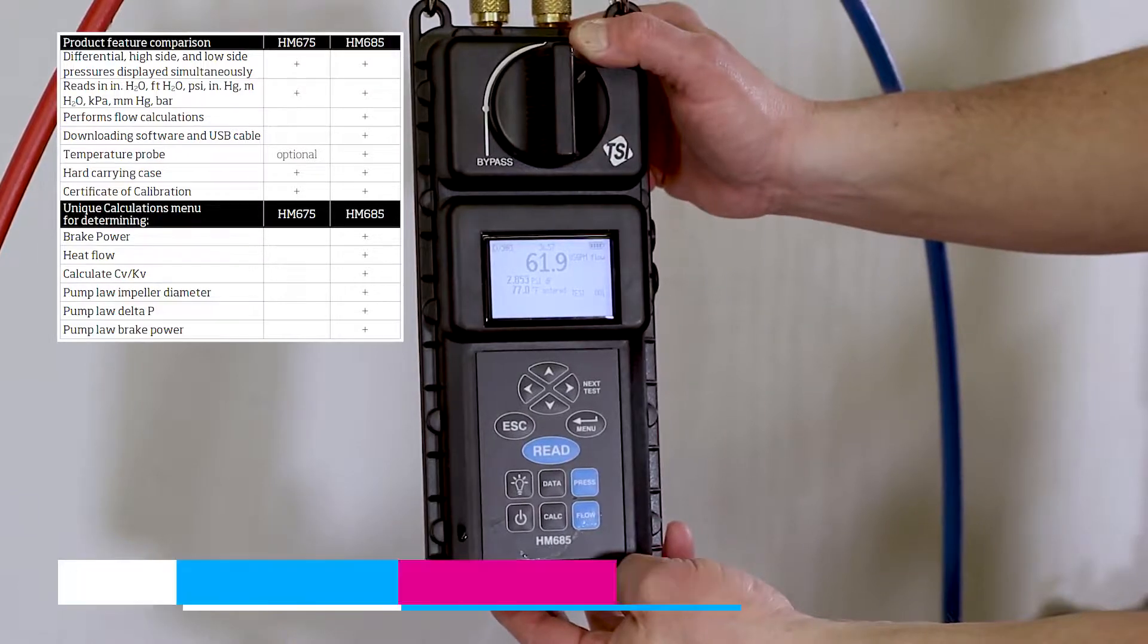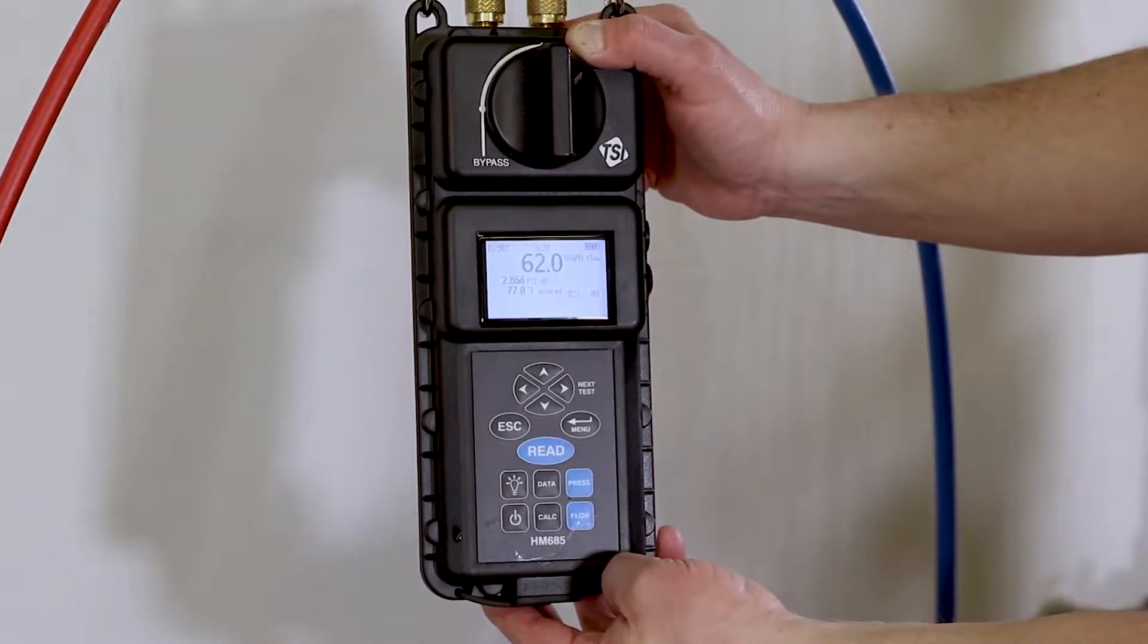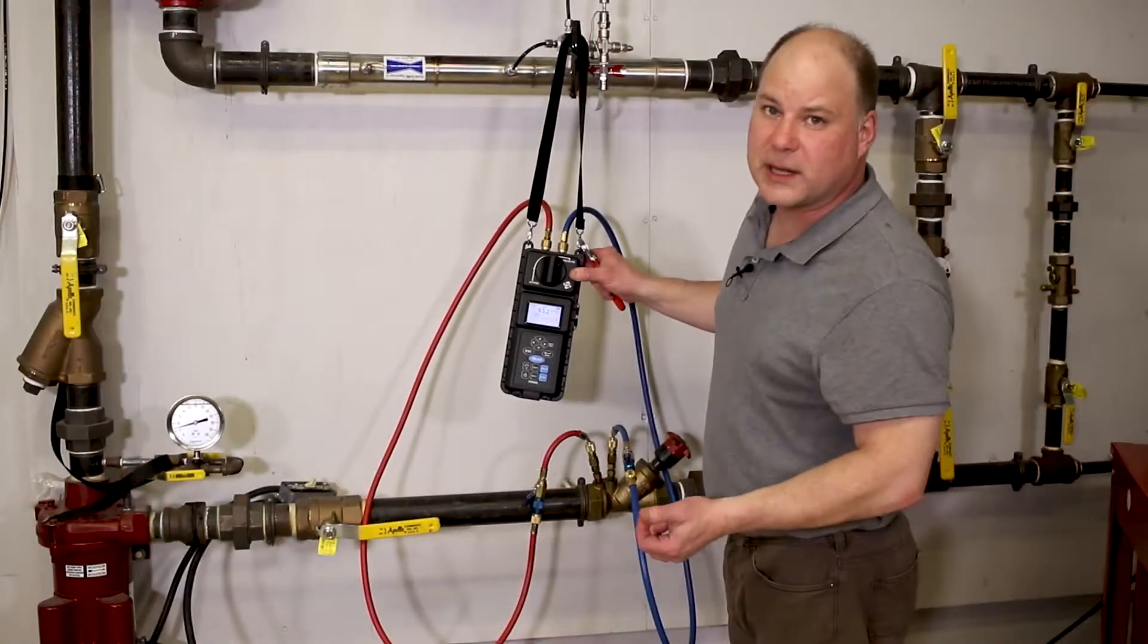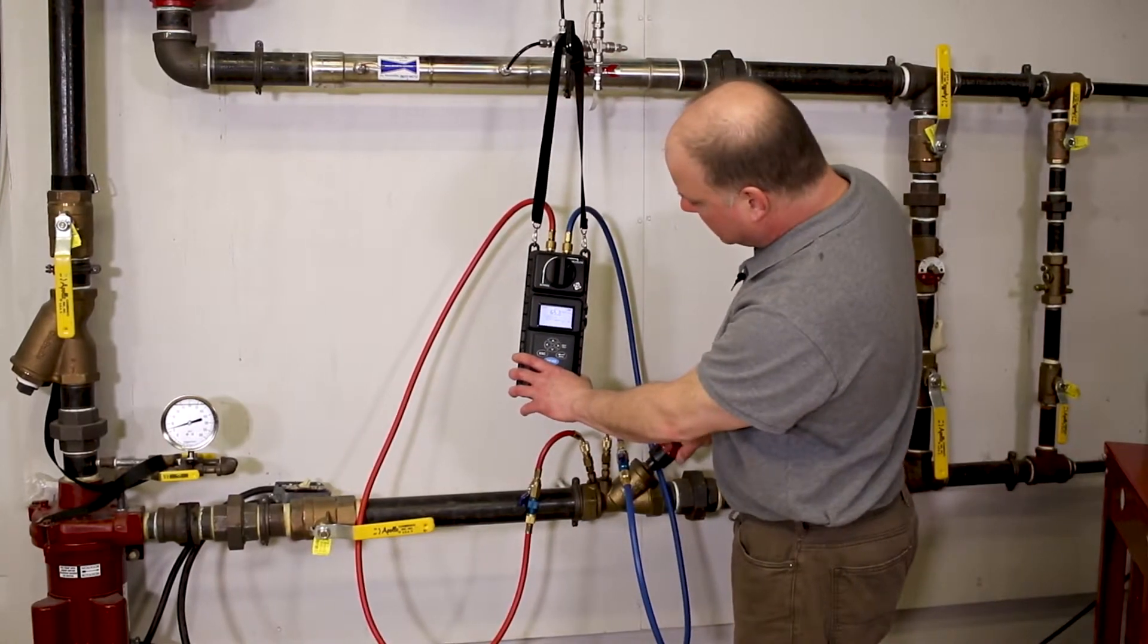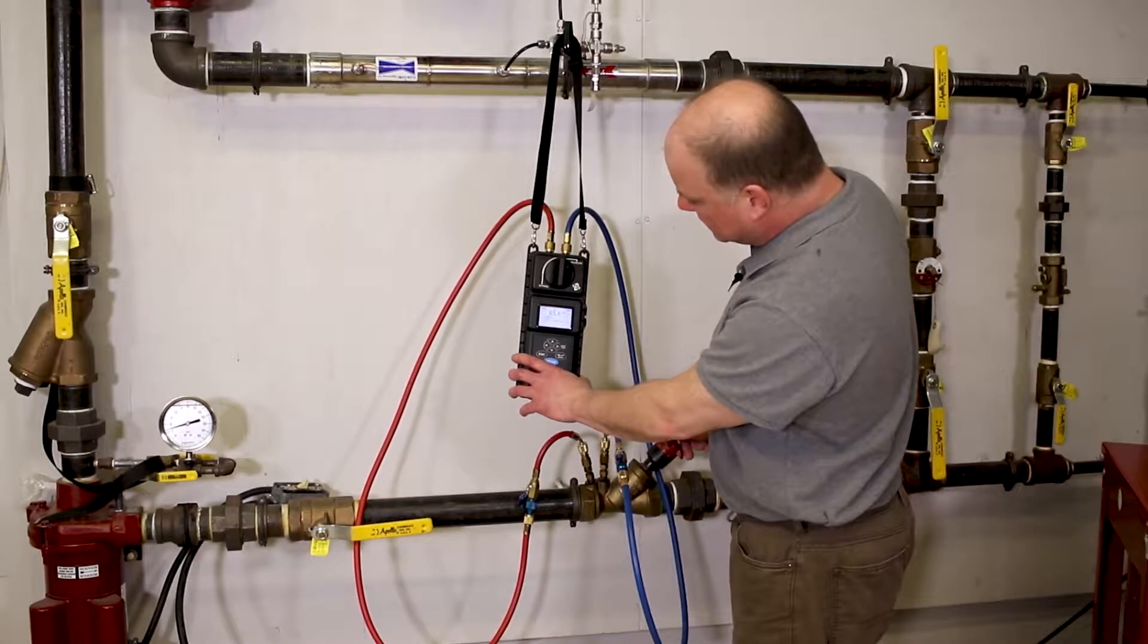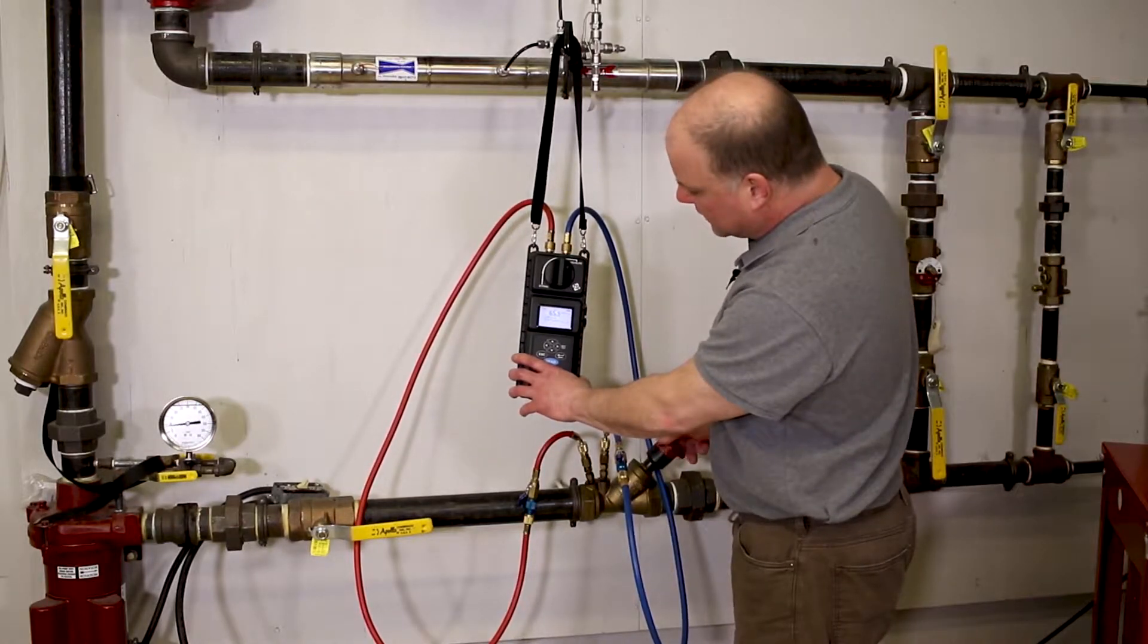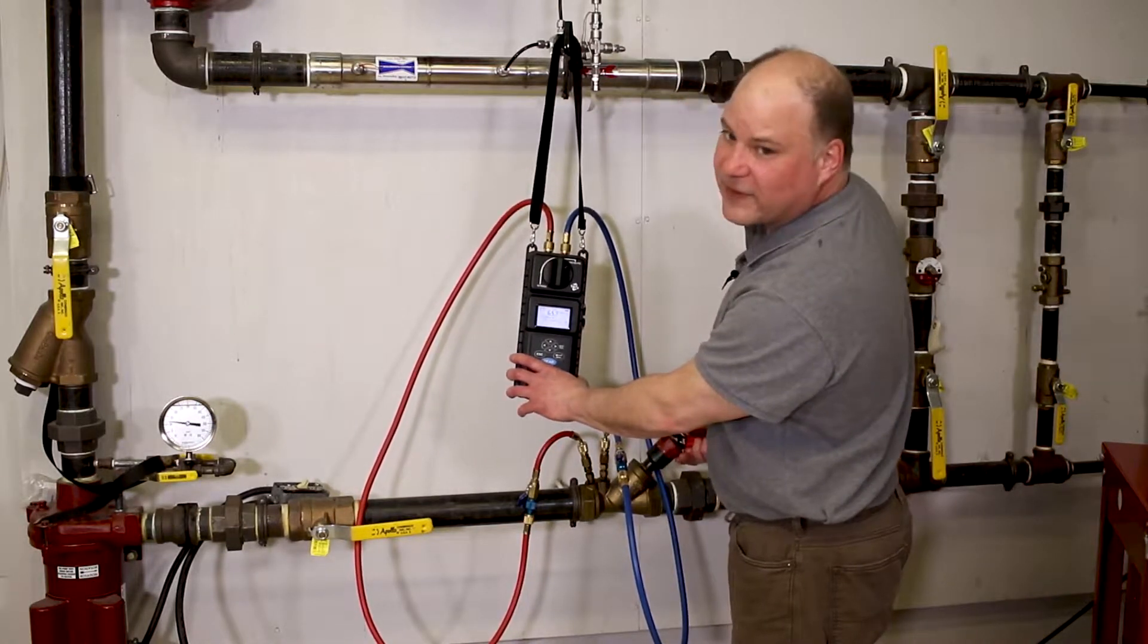I've programmed that in. I go to my flow setup, flow measurement, and we can see the flow in gallons per minute. At this point we're measuring 65.2. By adjusting the stem position, we'll be able to change the pressure drop across the valve and the flow.